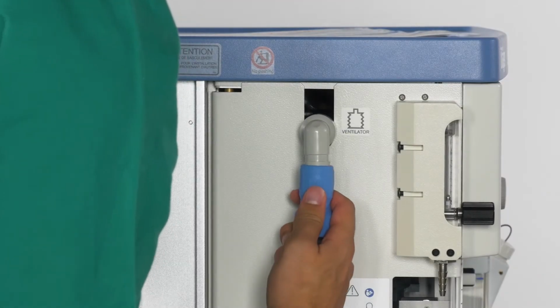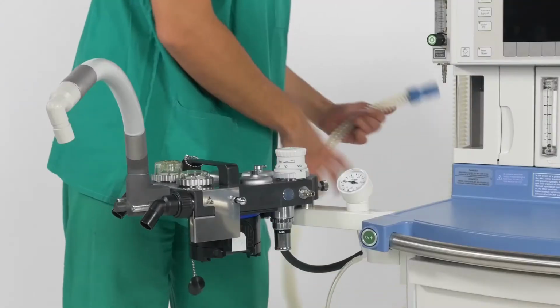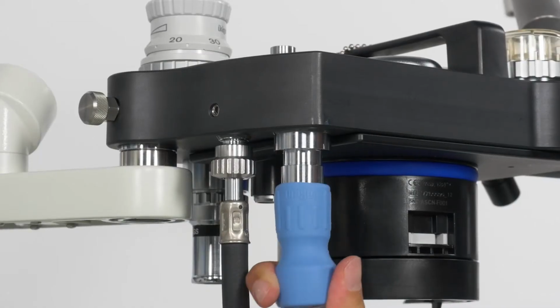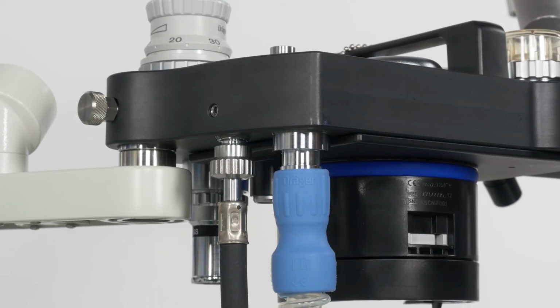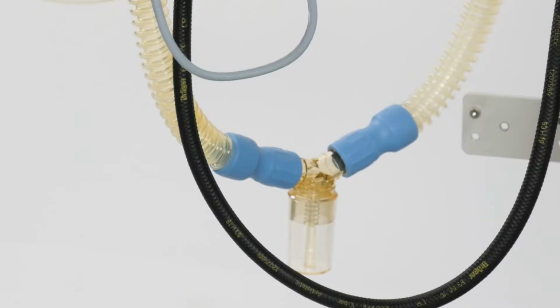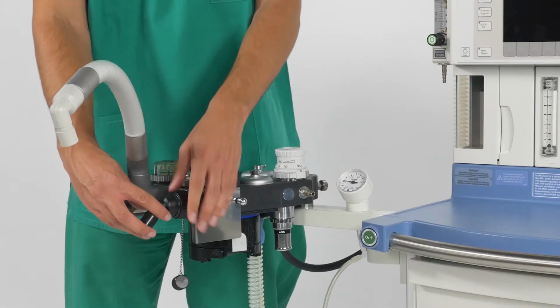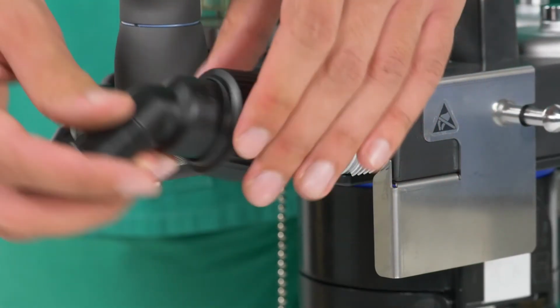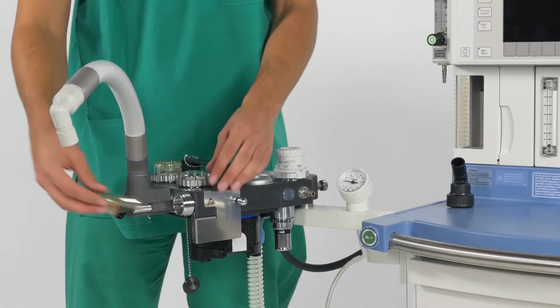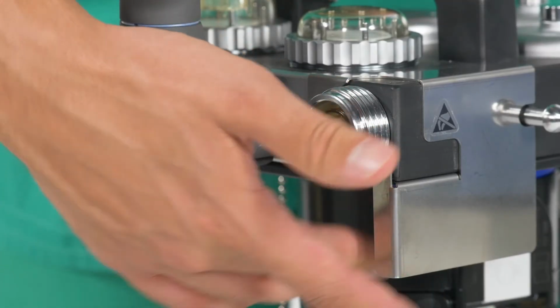Attach the ventilator hose to the piston ventilator and to the conical connector port on the bottom side of the COSY. Make sure that the optional water trap is at the lowest point of the connection. To insert the flow sensor, unscrew and remove the expiratory port from the COSY. Insert the flow sensor and reinstall the expiratory port.